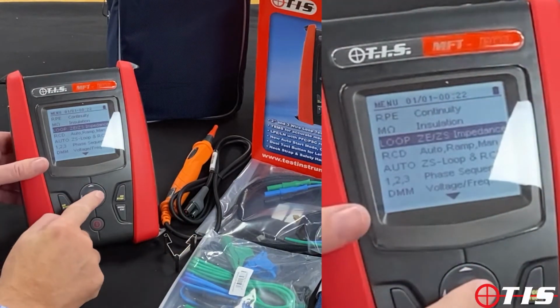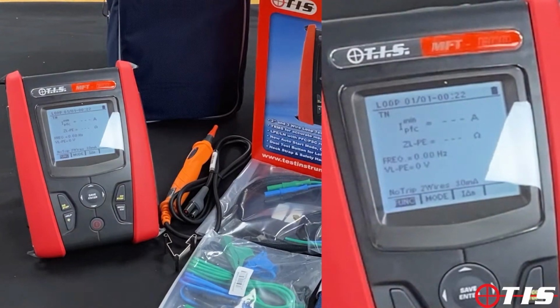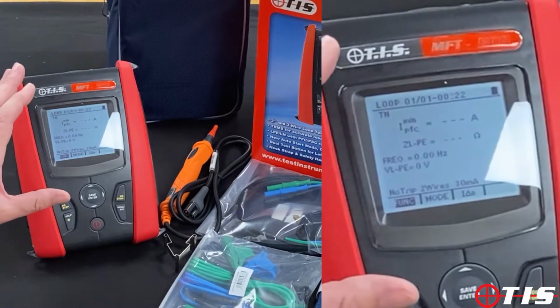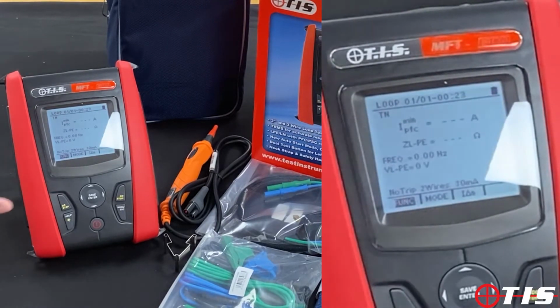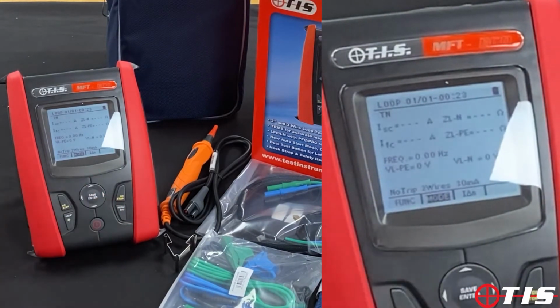Loop impedance. Big feature with this unit is the accurate two-wire loop test, particularly for testing at lighting circuits. With two-wire loop testing, it can be difficult to get repeatable and accurate readings. Because we've used a three-wire mesh method, this unit will give you accurate, repeatable two-wire loop tests. Obviously, we can do a standard three-wire test as well, and the big thing with all of the loop tests here is it will do live neutral, live earth, PSC, PFC loop tests just with one key press. So again, a big time saver.